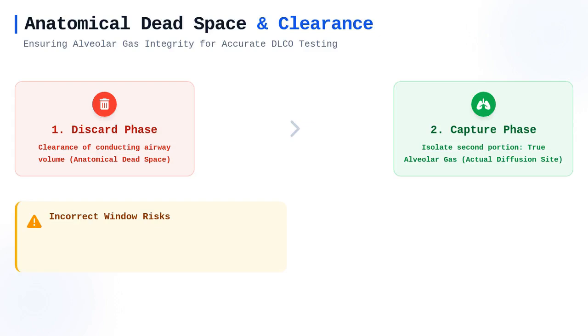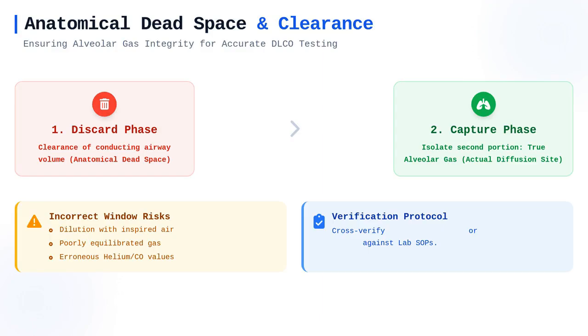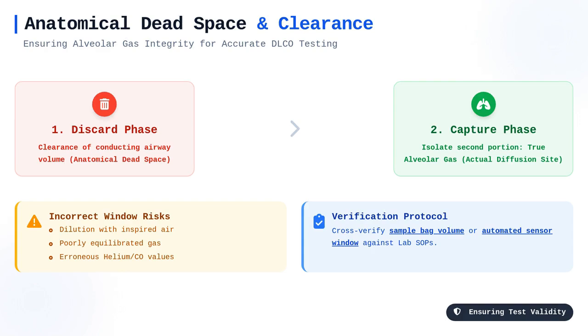If your mechanical dead space or anatomical clearance window is set incorrectly, you risk diluting the sample with inspired air or poorly equilibrated gas. Consequently, the helium dilution and carbon monoxide uptake values would appear erroneous, ruining the validity of the entire test attempt. Always verify the volume of the sample bag or the automated sensor window against the laboratory's standard operating procedures for the specific equipment in use.